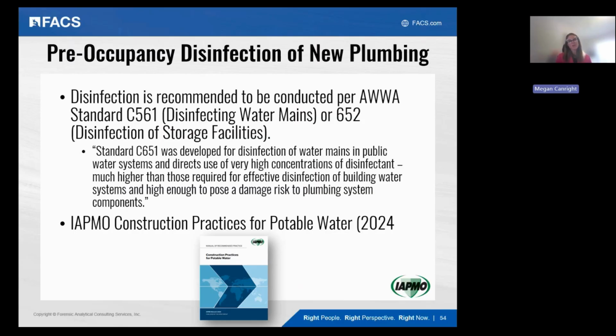The IAPMO construction practices for potable water document gives good recommendations about what's appropriate for disinfection of premise plumbing as part of commissioning new pipework, and this can also be extended to emergency disinfection. If a building is already built and experiencing a waterborne pathogen problem, this is still a good resource to rely upon.